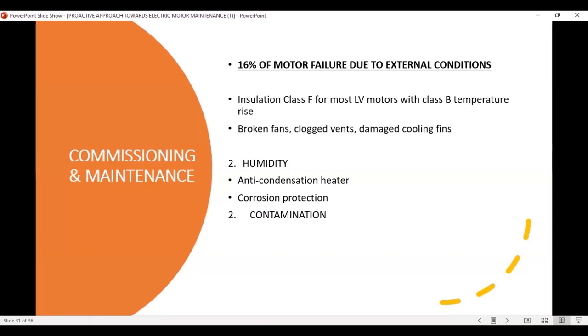External condition has been a lot of contribution factor of motor failure, like plugged vents and damaged cooling fins. All these issues, if not resolved, if you have a broken fan, the fan will not be cooling the motor enough, like I showed on the motor thermal capacity. The fan is supposed to operate constantly to cool down the motor.